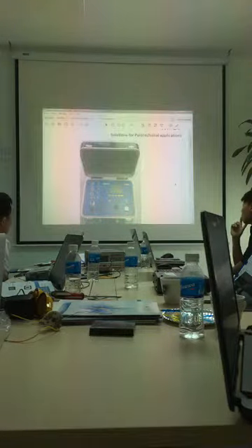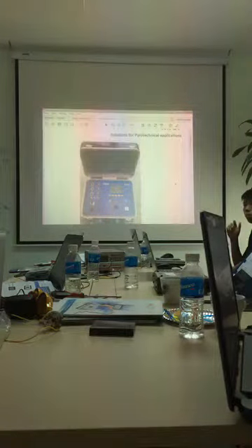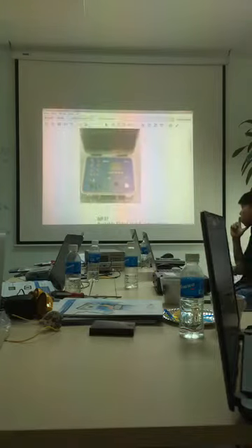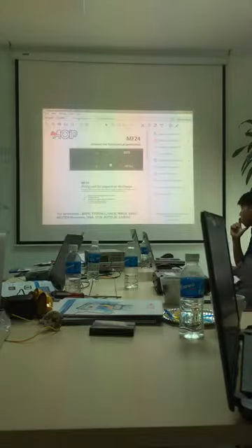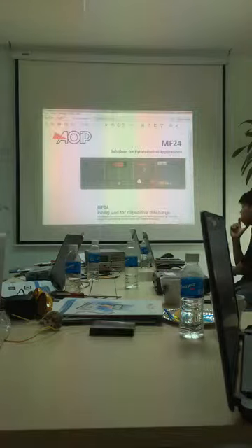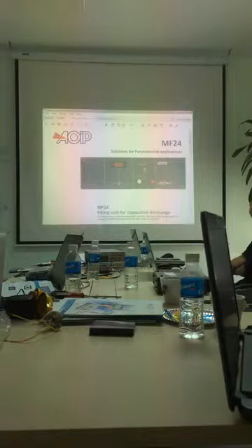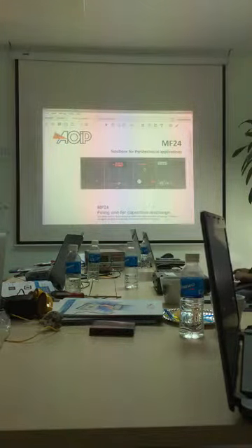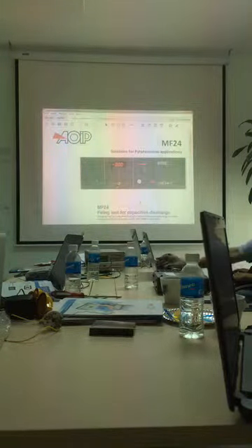The MF system is for ammunition manufacturers. We have to trigger the ammunition without having an explosion. So that's the same principle. It's resistance measurement, but it's highly secured. Those instruments are only micro-ohmmeter, ohmmeter, megohmmeter, but highly secure. You see there is a key there, because the objective is that not everyone should have access to that kind of instrument.